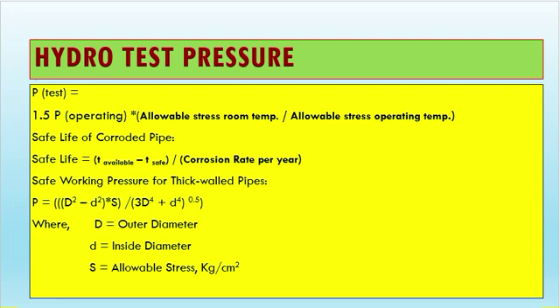The safe life of a corroded pipe is calculated as: Safe Life = (t_available − t_safe) / corrosion rate. This formula gives the remaining safe service life of a corroded pipe.